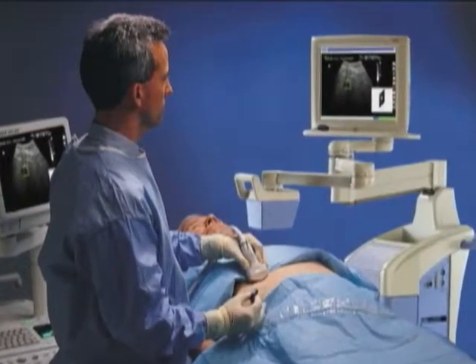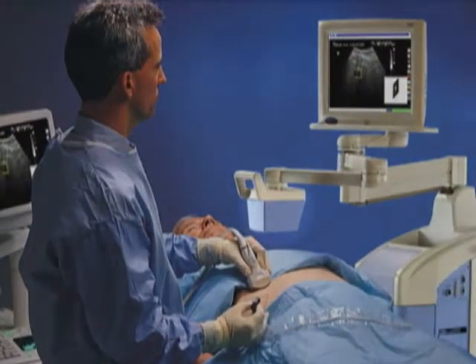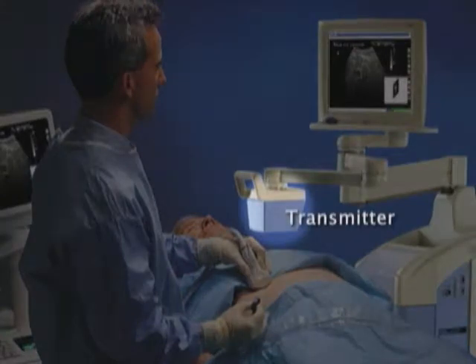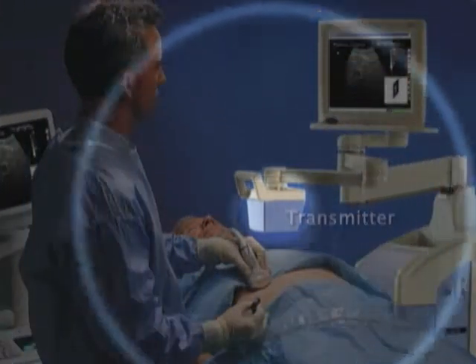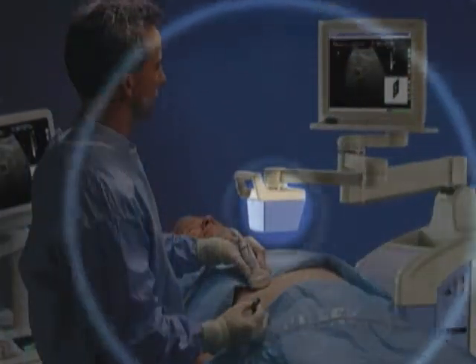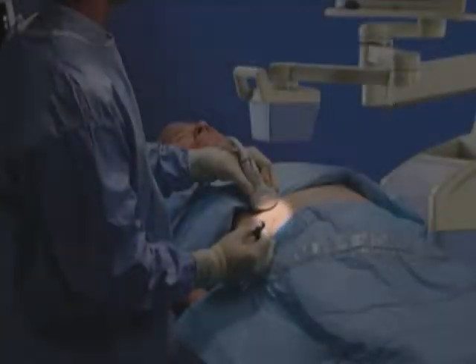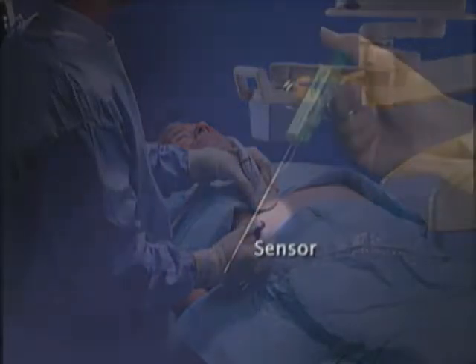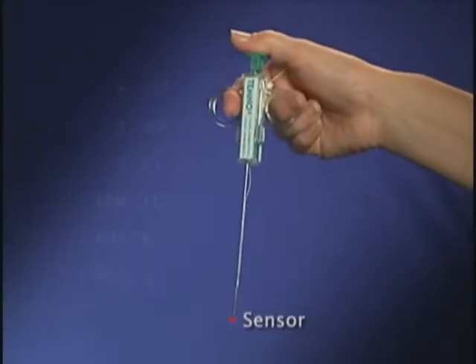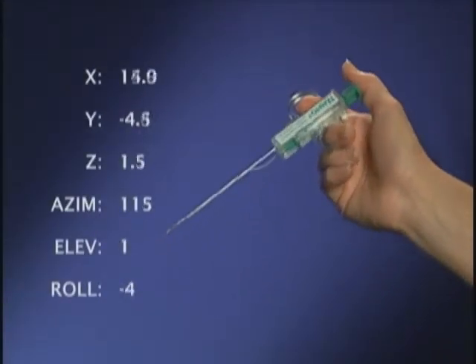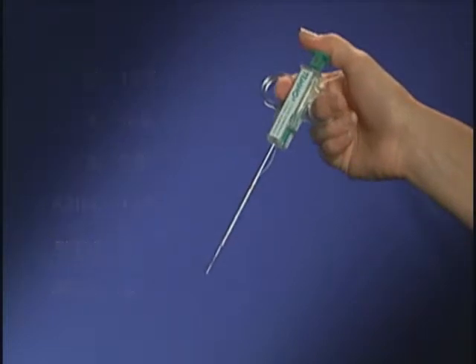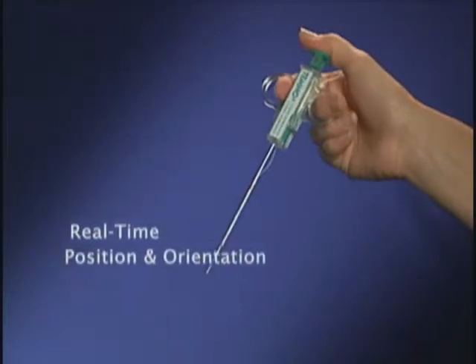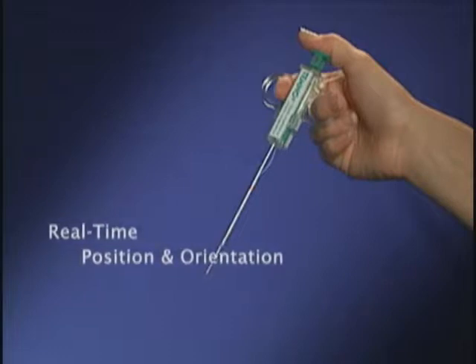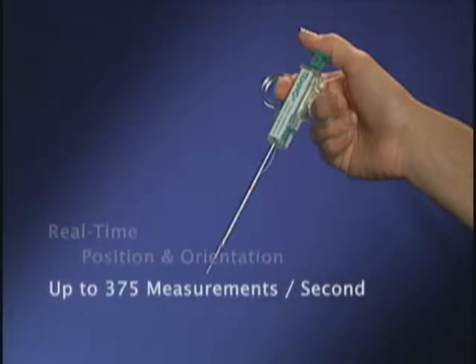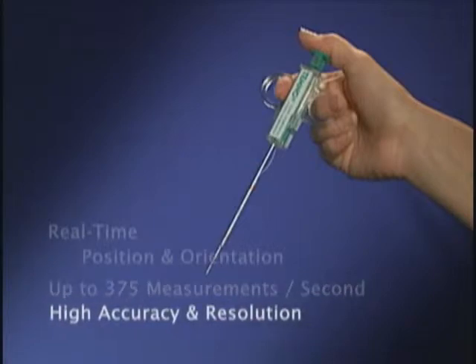Here's how this remarkable 3D localization technology works. A small transmitter placed near the patient generates a series of pulsed DC magnetic fields. The fields induce measurable voltage changes in one or more miniaturized sensors, typically attached to a body part and/or instrument. As the sensor moves through space, field changes are recorded and reported to an electronics unit. These data points enable the calculation of the real-time position and orientation of the sensor in free space. Up to 375 measurements are made per second with high accuracy and resolution.